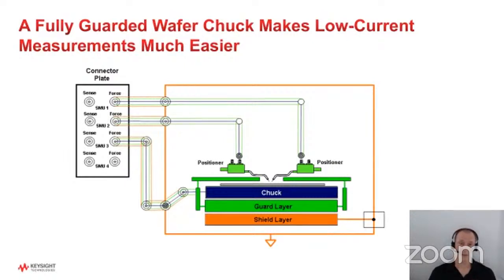Remember earlier when I talked about triaxial cables and explained that there's a driven guard, so you have the center conductor, then a driven guard, and then the outer ground shield. You can actually do the same thing with a wafer chuck, believe it or not. There are manufacturers that have guarded chucks, as shown in this diagram. The effect of doing this on a wafer is similar to the benefit you get from doing it on a cable: it eliminates a lot of the stray leakage currents you would otherwise see. So you can make low-level current measurements much more easily and reliably if you have a guarded chuck on your wafer prober.